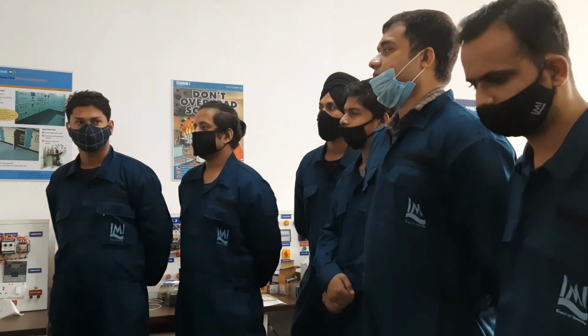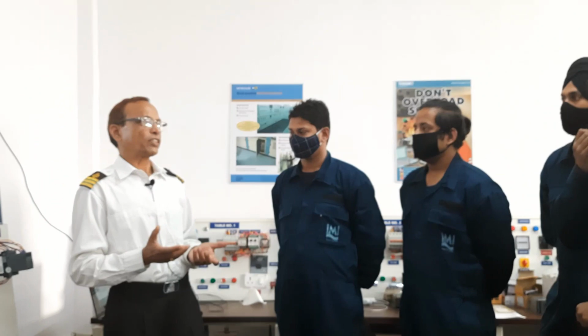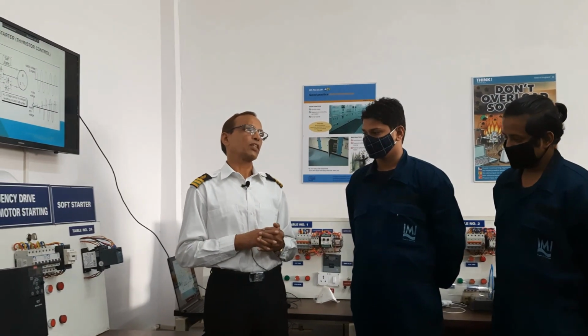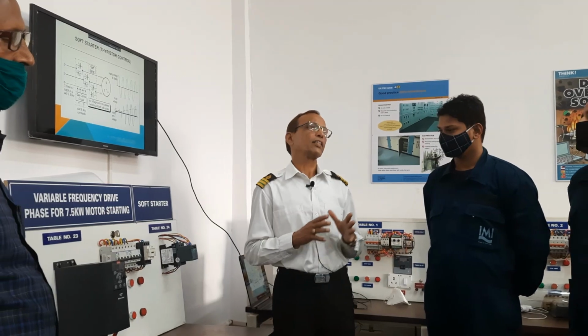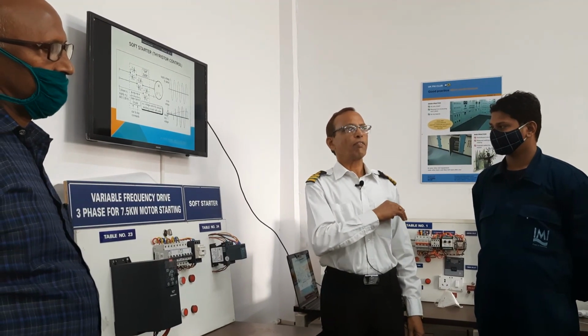The voltage regulator, or AVR, automatic voltage regulator, is controlling your dip. 15% dip is being controlled by the AVR in 1.5 seconds, so you will not have a very big fluctuation.